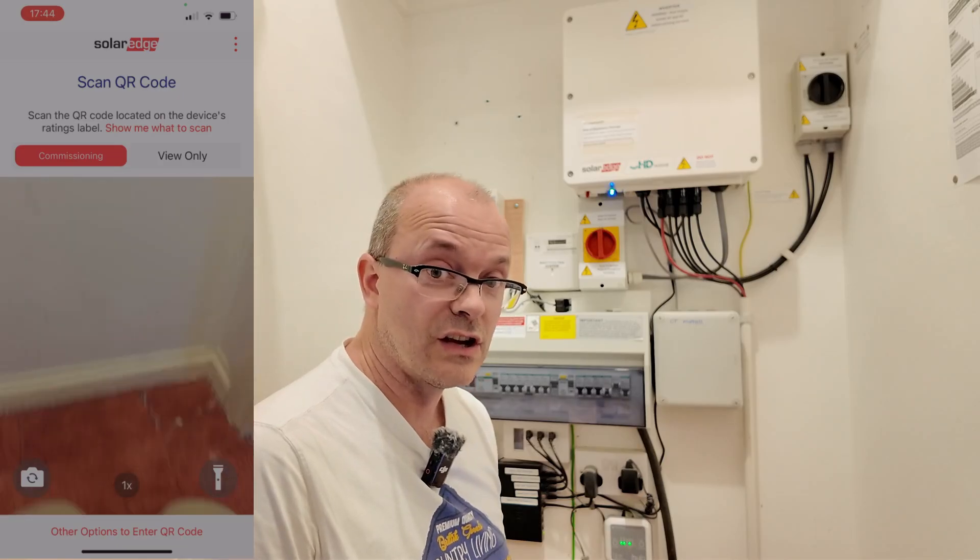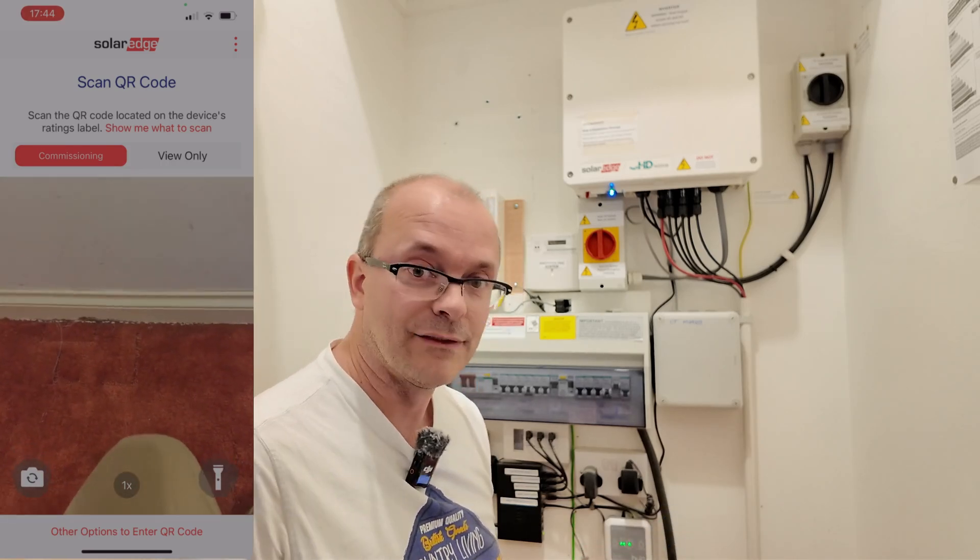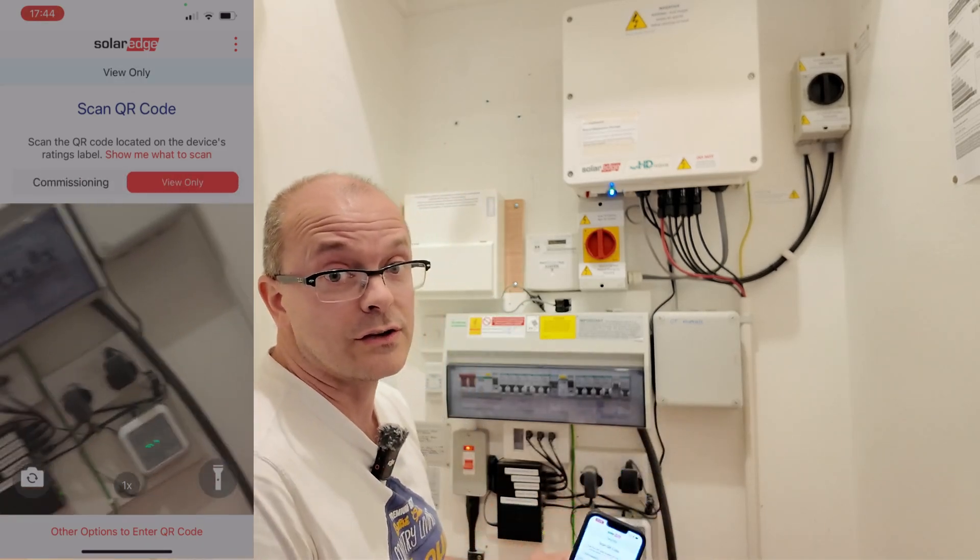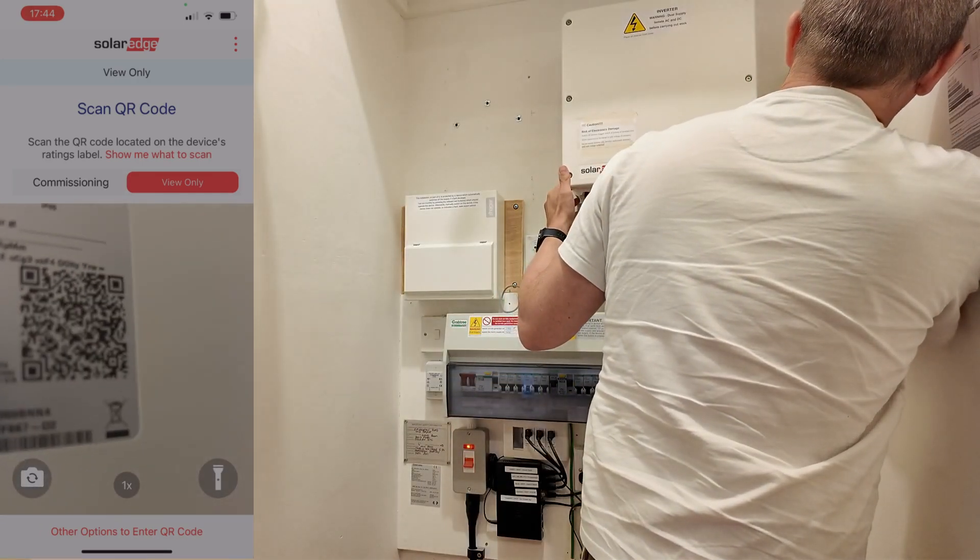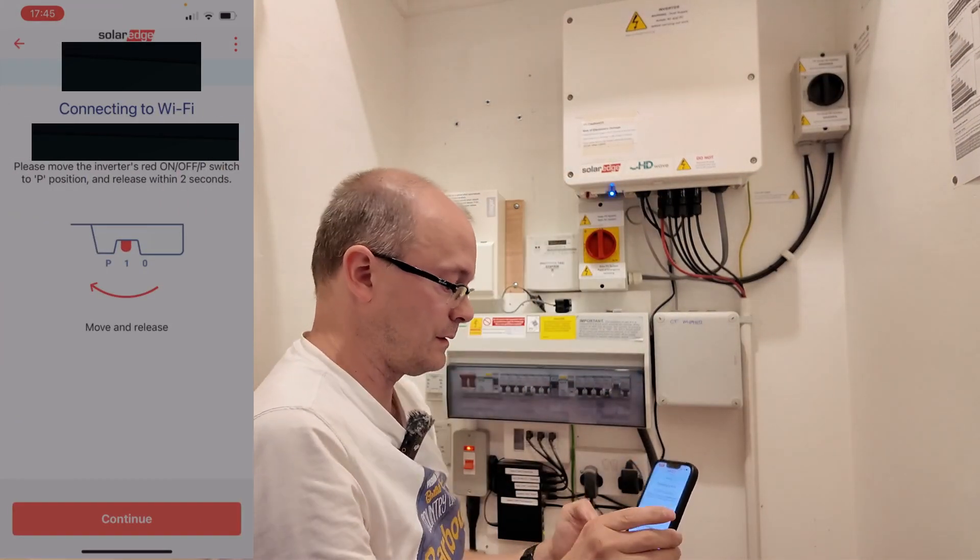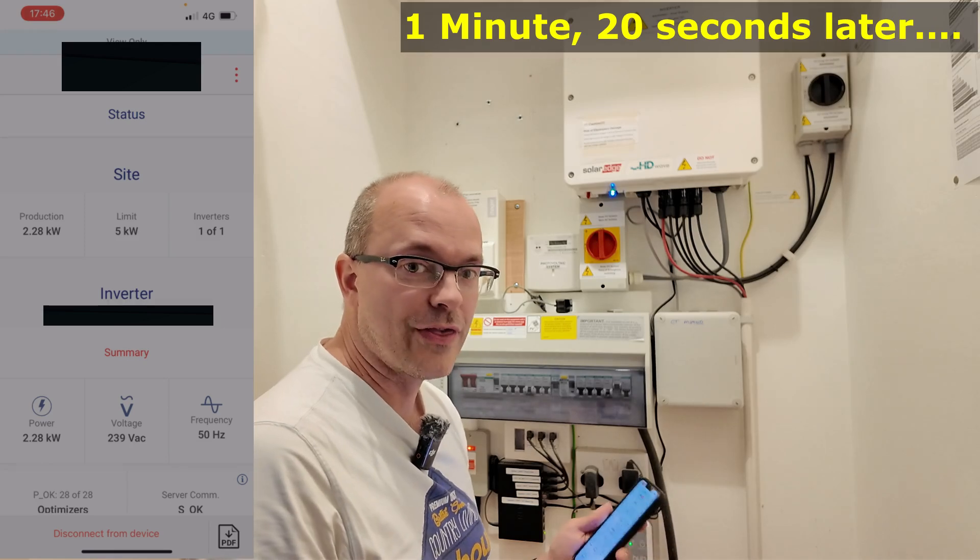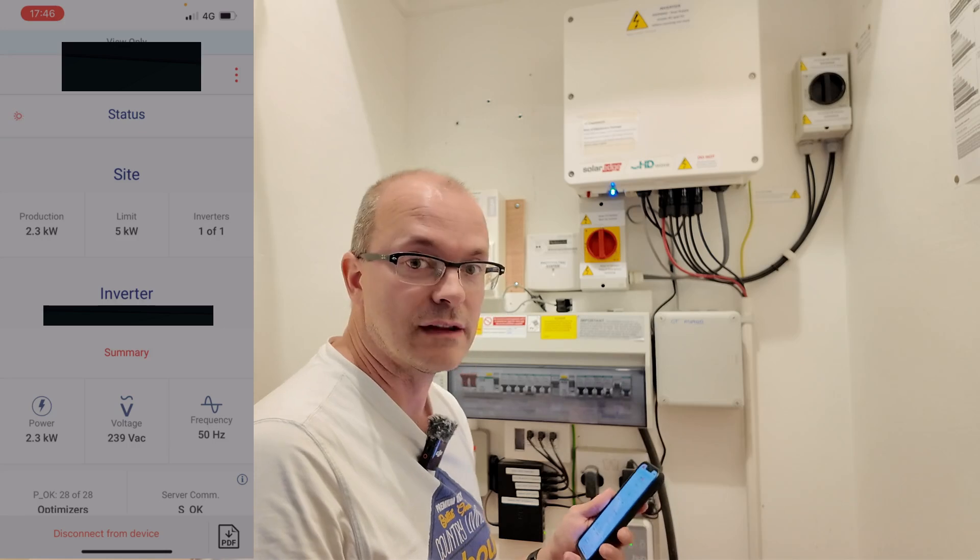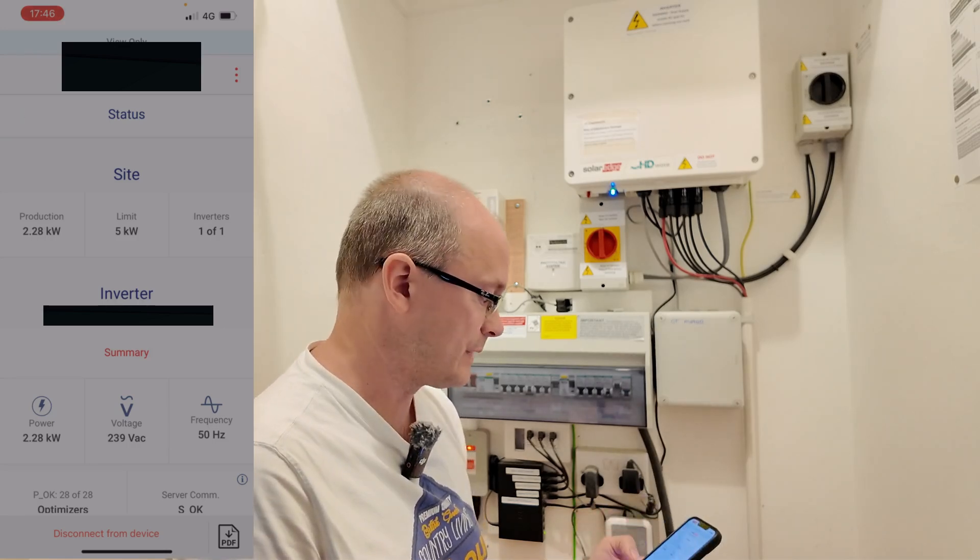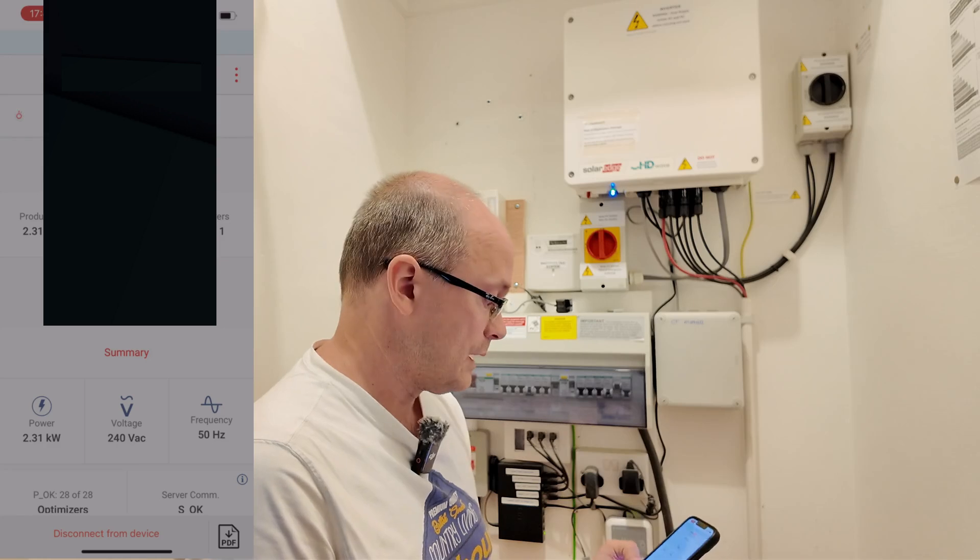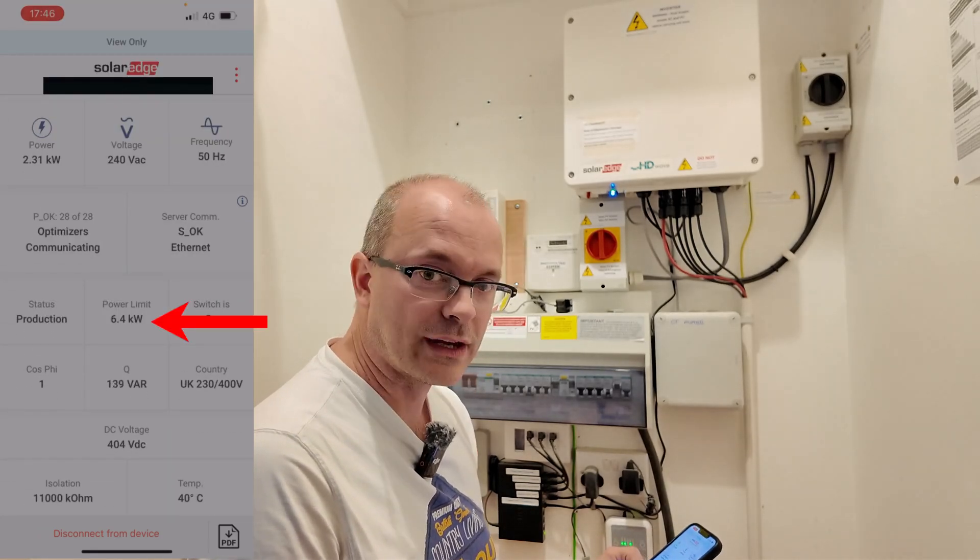What we're going to use is another app called SetApp. This has got two options, commissioning or view only. If you don't have an installer account you can go onto view only. We'll scan the QR code on the side of the inverter, set this to P and let go and tap continue. Wi-Fi now connected. This is what the installer will see when making settings. You can view all of these in a read-only format even if you don't have an installer account. As you can see we have got a 5kW site limit, that's your export limit. But if you scroll down there is a power limit 6.4kW.